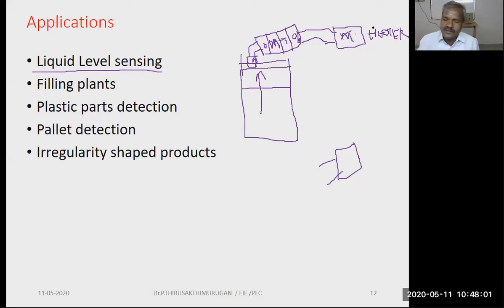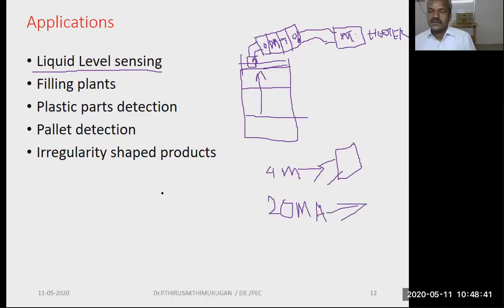A similar setup is nowadays available with a 4 to 20 milliampere range in digital format. When there is no signal, the output is 4 milliampere, meaning the water is at the bottom. When the current generated from the circuit is 4 milliampere, the motor should be on. When the proximity sensor senses the liquid level reaching the high level, the output can generate 20 milliampere. So the 4 to 20 milliampere signal is used for industrial applications. The same inductive and proximity module setup is available with 4 to 20 milliampere output: for a lower level, 4 milliampere output, and for a higher level, 20 milliampere output. So 4 to 20 milliampere is the industrial current sensor, or current transmitter, range.